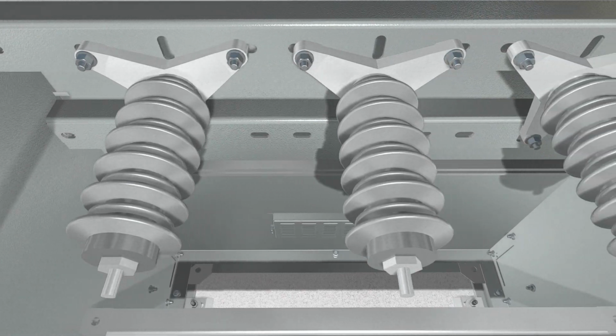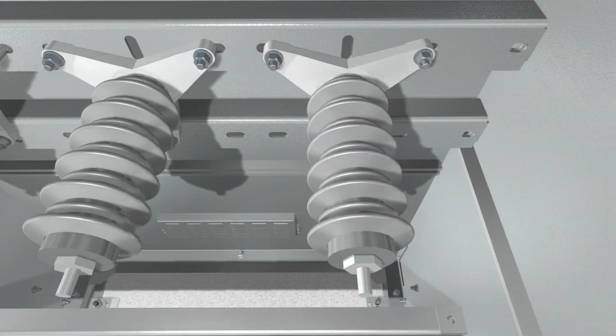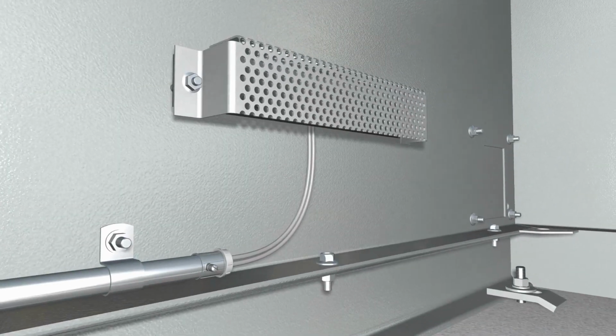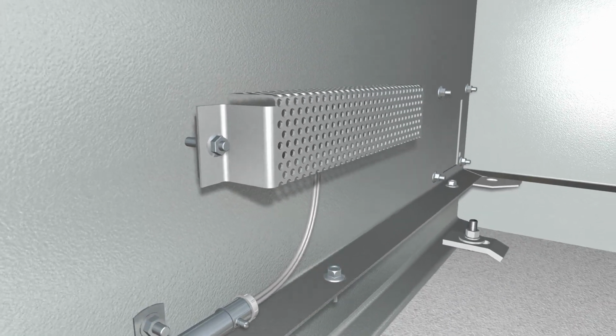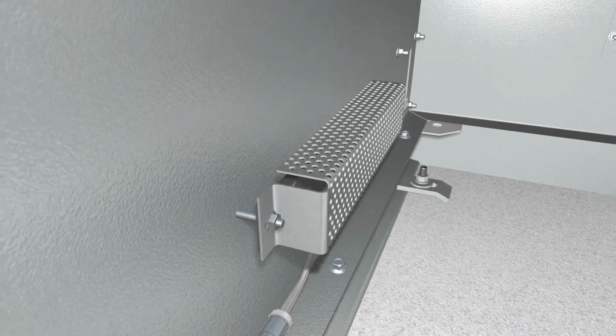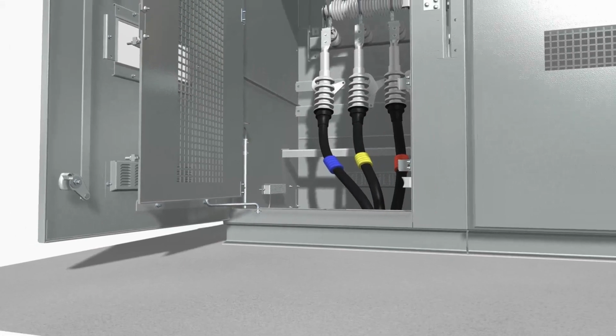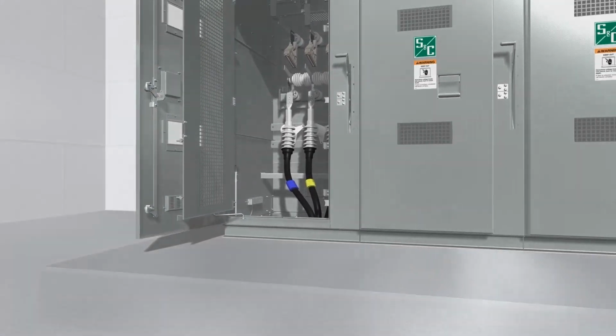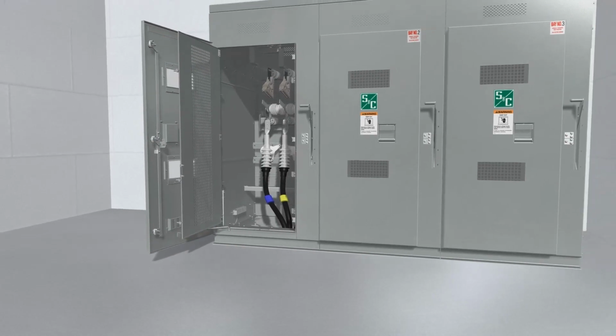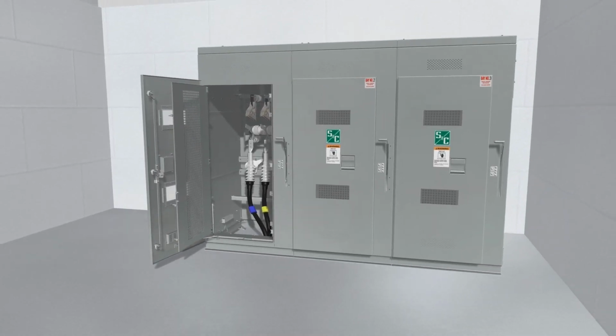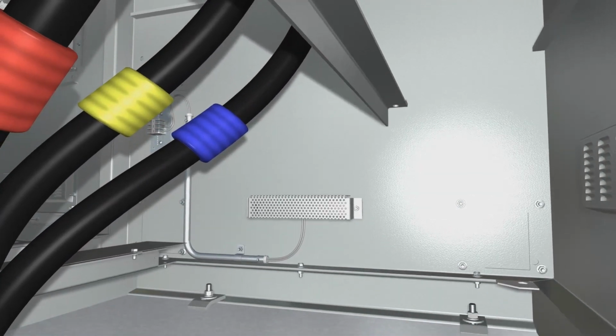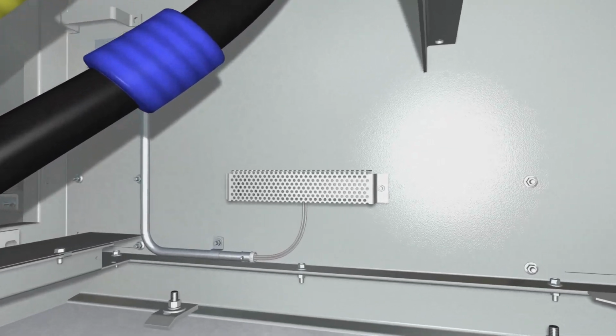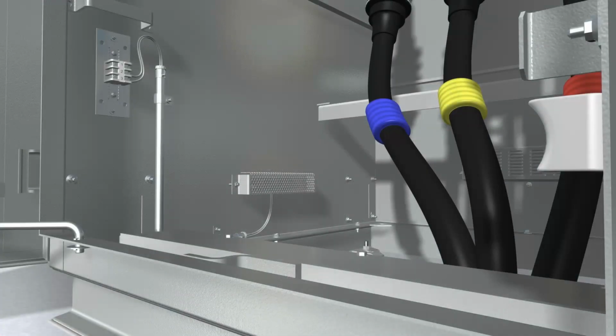Step 19. Install and connect the surge arresters if applicable. Step 20. Strip heaters are included as standard in all S&C metal-enclosed switchgear designed for outdoor installation. They are also optionally available in indoor switchgear to maintain the enclosed apparatus and interior areas free of condensation, which, if allowed to accumulate, can contaminate insulation and promote corrosion. Therefore, when strip heaters are included, make sure they are connected to an adequate power source and energized before placing the switchgear in service.